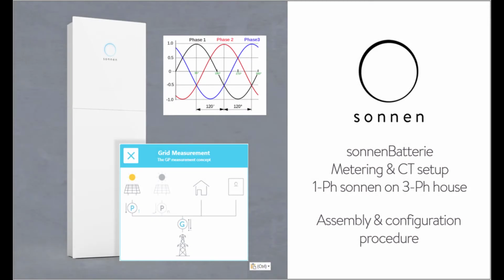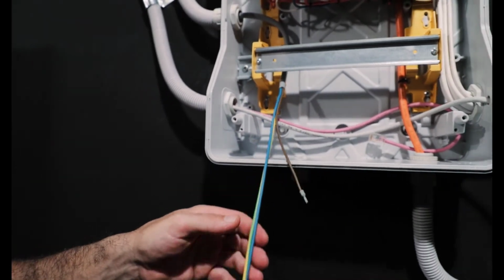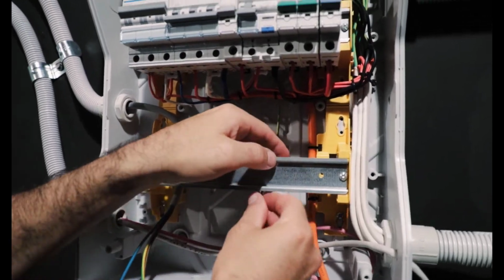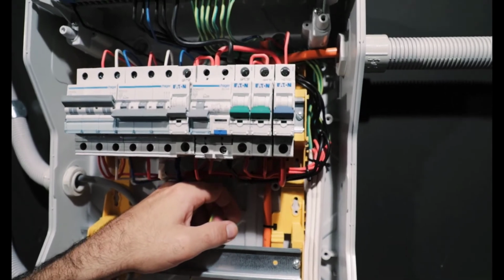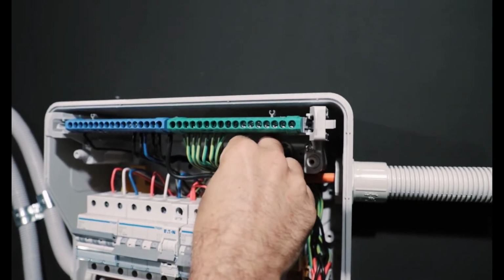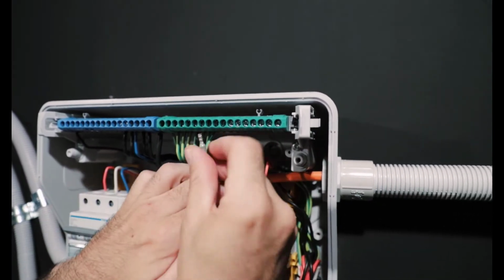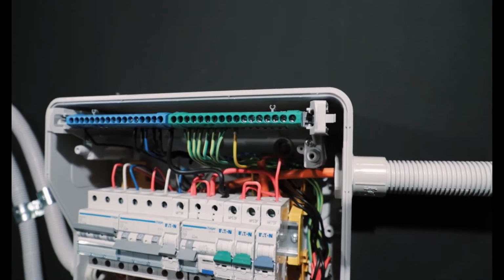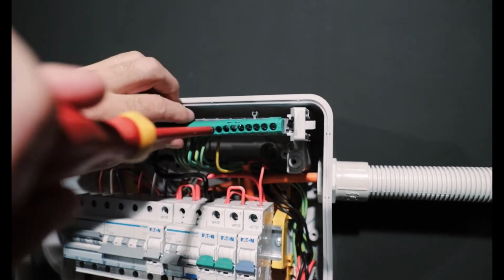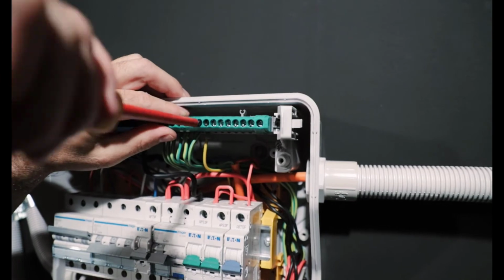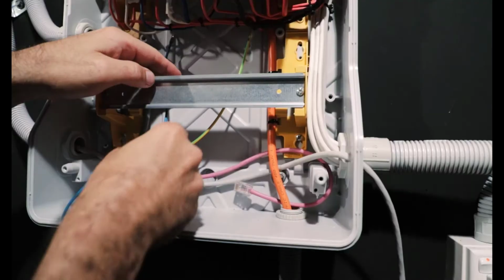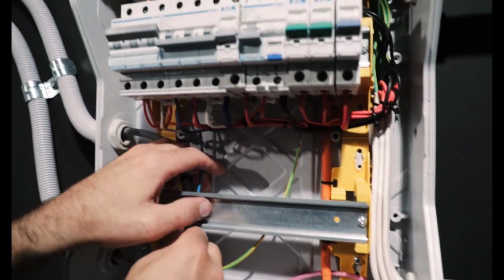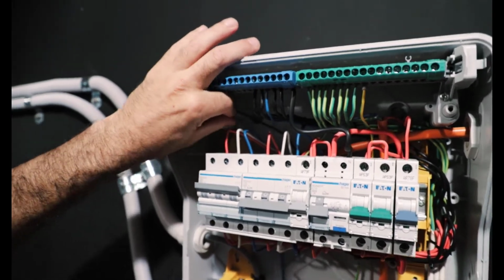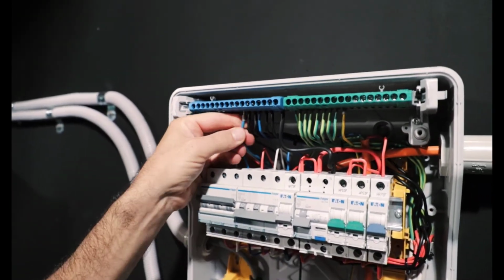Now let's look at a slightly more unusual one, where we're going to be putting a single phase Sonnen system onto a 3-phase property. So here we have a 3-phase board. So we just wire the single phase Sonnen AC connections into that. Now obviously with a 3-phase board, you have the option of wiring the Sonnen system onto either L1, L2 or L3. Now for this example, we're just going to put it straight onto the L1 configuration.